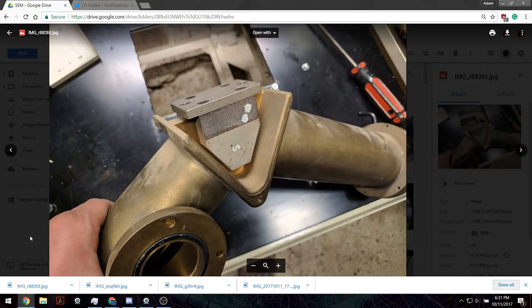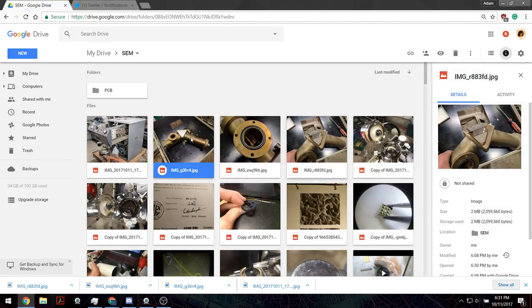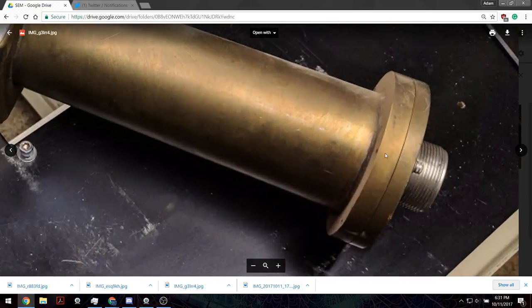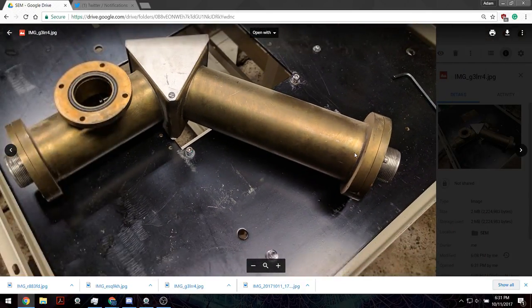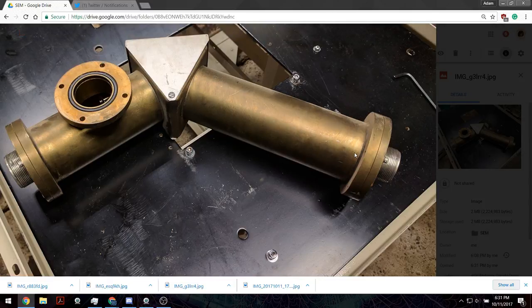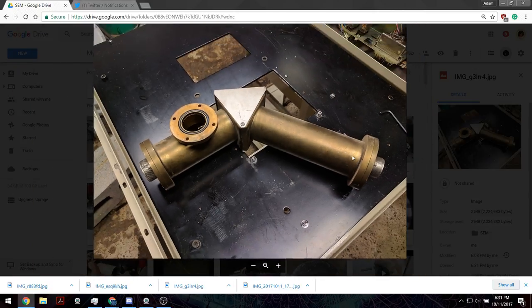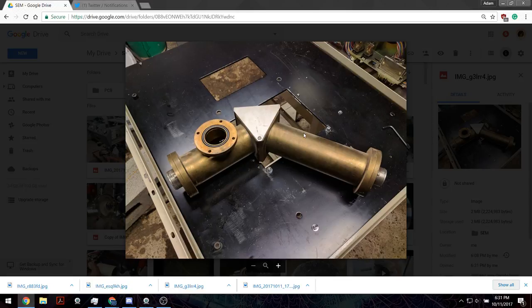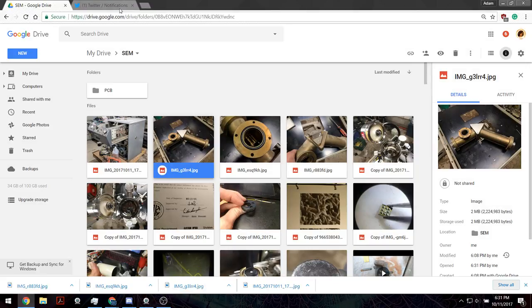And as it bends it around the corner, only the helium gas will make it to the end down here, and then at the end there's basically a Faraday cup, and a Faraday cup is something that just looks at the net change in charge, or it basically counts the ions that hit the Faraday cup. So by counting the ions that hit it every second or so, you get a rate, you can see how much gas is leaking into the system, and using that you can determine, okay, where is this leak coming from? So that's the analysis tube, and we'll head back to the webcam now as we start to actually tear into some components on this thing.